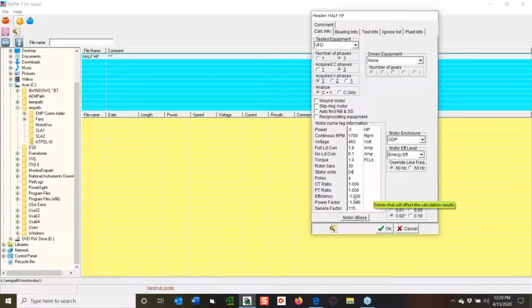I can put numbers in here if I want. If I put in some other number, like 0 or something like that here, it's incorporated into the torque reading, so I usually leave that. It is a fan motor, and obviously with that efficiency we'll call it standard.